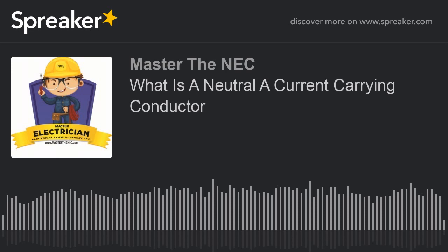Whereas we know that current is always traveling on the neutrals at any given time, generally speaking. A totally, purely balanced three-phase load might have nothing traveling on the neutral, but we're going to keep it very general here. Most of the time, you're not going to get something that balanced out, so you'll have neutral current. Now, you could have a motor or something downstream that is three-phase that you don't even take a neutral to because you don't need it.